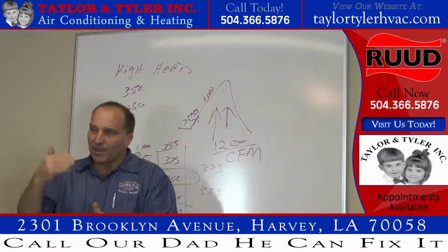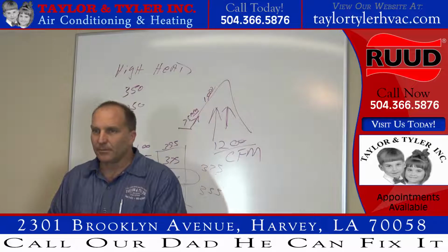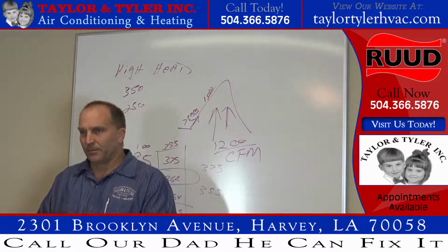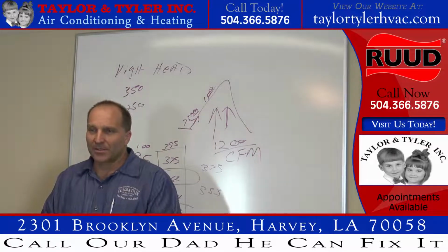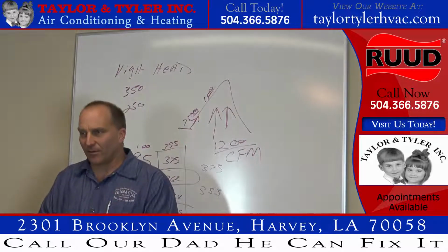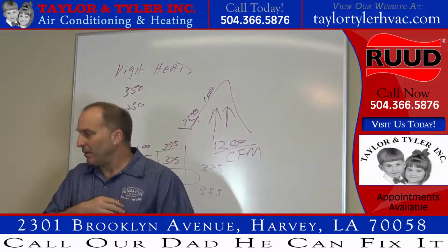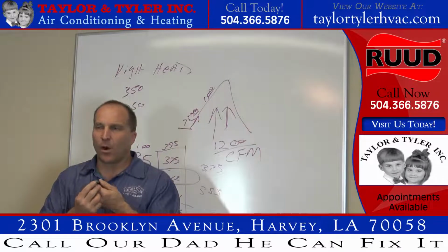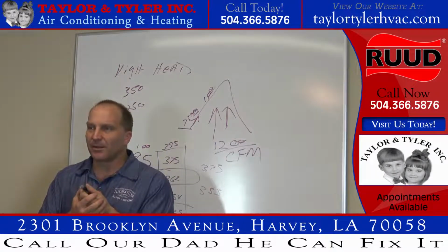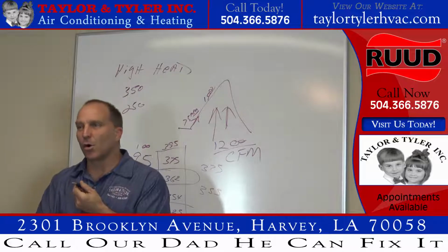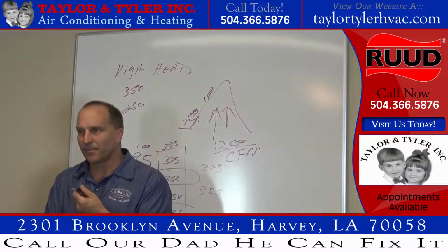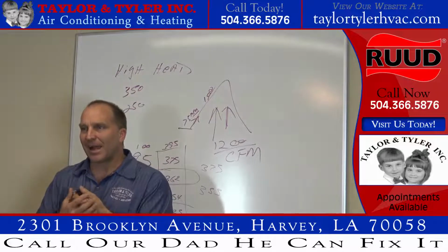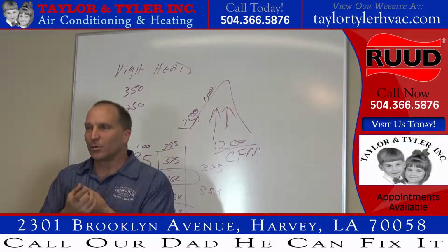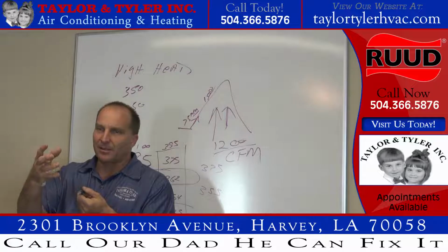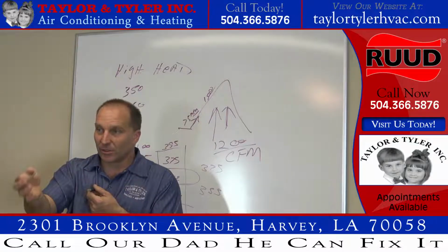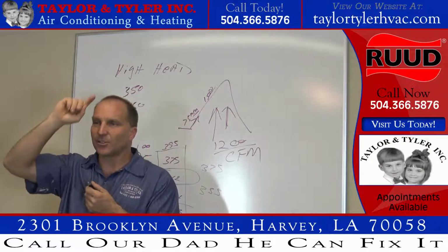Now what's going to happen on the other side of the dryer? It's going to start getting cold. Okay, why is it getting cold? Because now your dryer is acting like a metering device. Just like a piston with a hole in it that drops your pressure on the other side, because it drops in pressure, it makes it colder. Pressures and temperatures coordinate together, right? Yeah. So in this case, your dryer is acting like a piston. It restricts the refrigerant through the system, and it makes the other side of the dryer, which is your liquid line, sweat. You'll see your liquid line sweating.